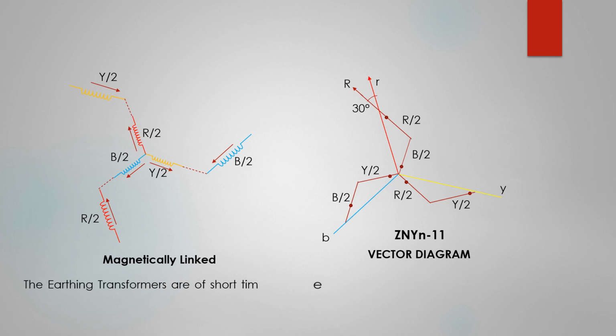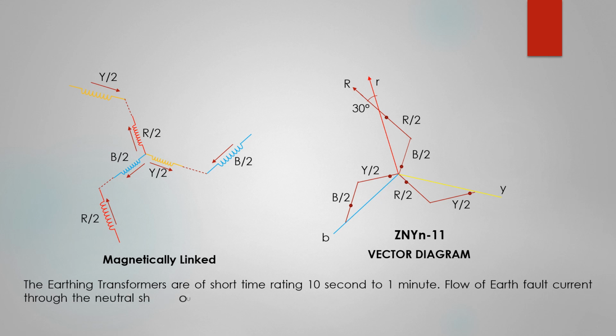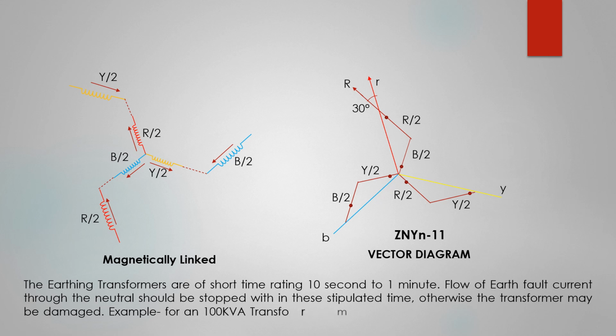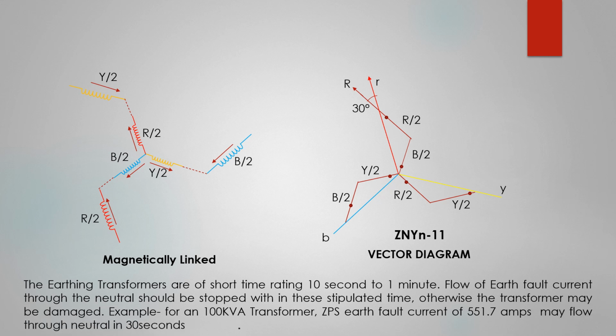The earthing transformers are short time rated, from 10 seconds to 1 minute. The flow of earth fault current through the neutral should be stopped within this stipulated time, otherwise the transformer may be damaged. For example, for a 100 kVA transformer, a zero phase sequence earth fault current of 551.7 amperes may flow through the neutral for 30 seconds. The flow of earth fault current through the neutral should be stopped within 30 seconds.